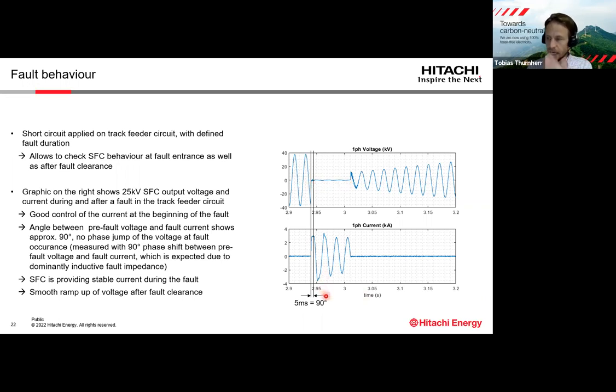So the way I've indicated it here is, if the voltage continues with the same angle, or without an angle step at the beginning of the fault, this means that the current during the fault should have an offset of 90 degrees to the voltage before the fault, because the fault impedance is basically inductive. And this we can detect here.